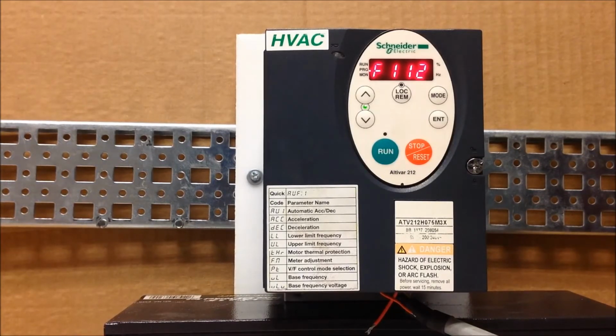Also keep in mind that not every single fault can be reset like this. There are some severe faults, like a short circuit fault, that it will not just allow to reset, and some faults also require you to power cycle the drive, meaning you have to make sure you kill power to it, and you wait till the display is blank, and then you power it back up, and see if the fault has gone away. So the last thing is, of course, the actual fault condition, whatever that may be, if it can be reset with a logic, that actual fault condition has to go away.